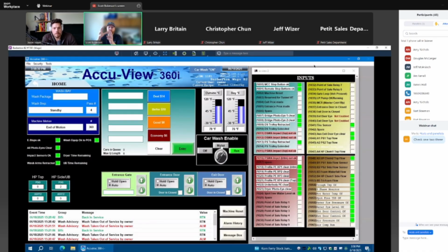So there is a very large possibility that you lose the phase that isn't controlling all those other equipment, so they can still pay, doors will open, all those other things will happen because they're on the other phase. So you always want to put it in maintenance until you get that confirmation that you'll have all three phases back, then put it in to run.